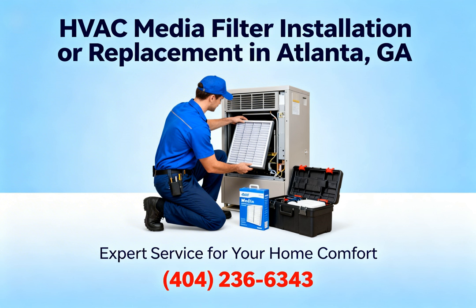But the signs of failure are pretty clear. You'll see shifts in the home's baseline environment. A noticeable reduction in airflow coming from the supply vents is usually the first mechanical symptom. Like it's just not blowing as hard. Exactly. And if the system's running constantly but the house isn't cooling down, or your energy bills spike unexpectedly without a change in weather or thermostat settings, the filter is likely fully loaded and restricting flow.